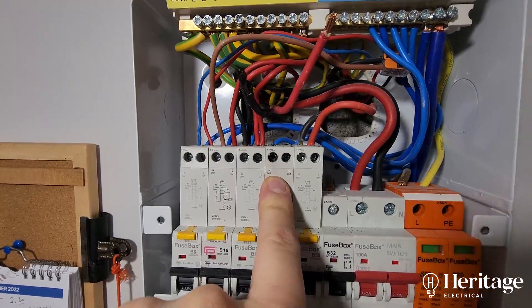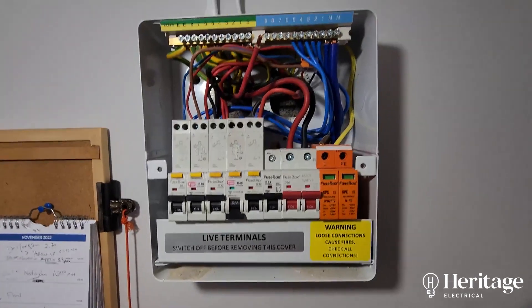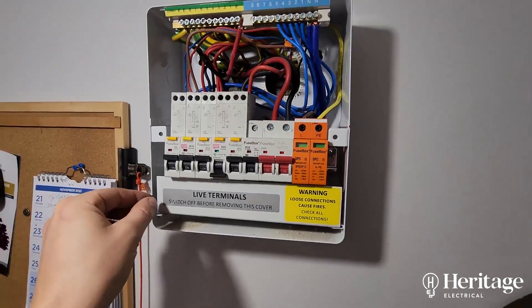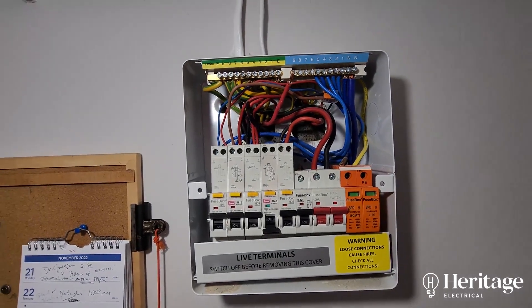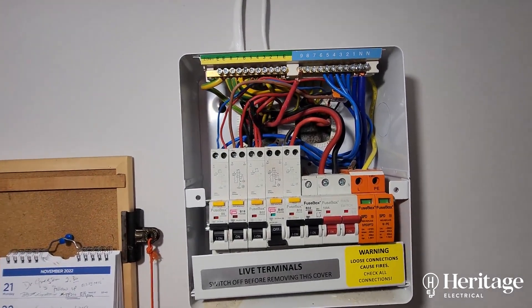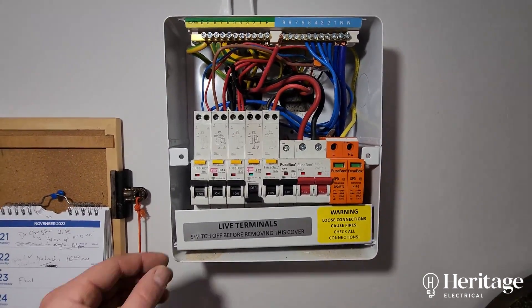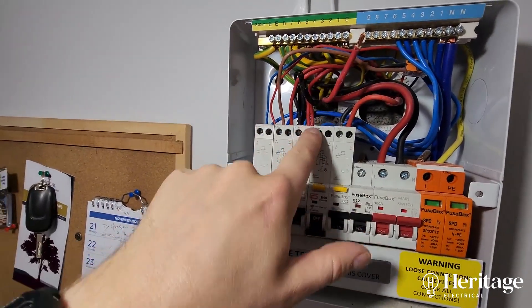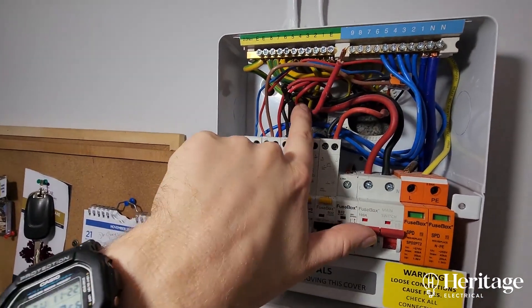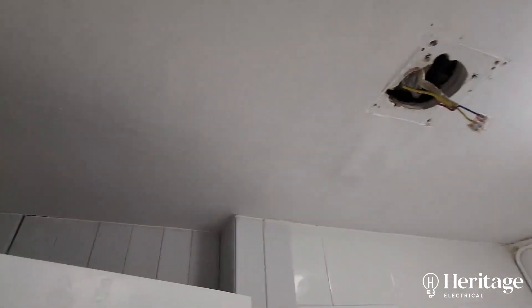The sockets - this one was completely loose, live and neutral, and the neutral in here was loose too. It's had a bad job done of the installation and it's not been certified or signed off. Apparently it was a couple of ladies that owned this place, turned it around, did some refurbs, had a slapdash job done. Martin bought the flat and inherited these issues, which have come to light through the tripping RCBO due to overheated cables and the blown main supply due to poor installation.